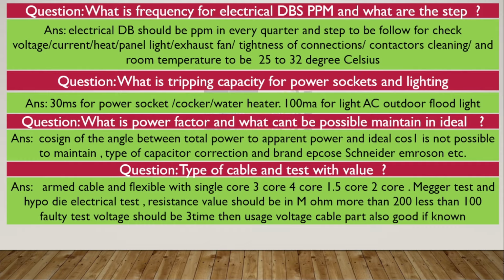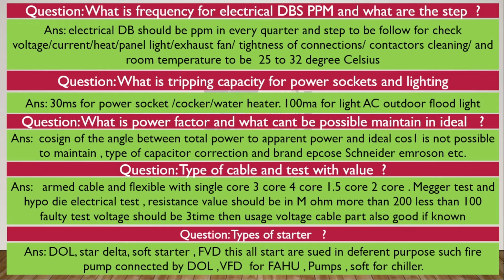And the Megger voltage should be about 3 times higher. Suppose we are testing a single phase cable at 220 volts, then we perform the test at 500. Same in 3 phase, where we perform the test at 1000 volts. These are the standards.